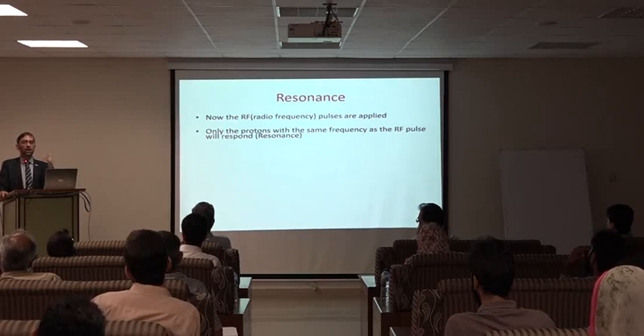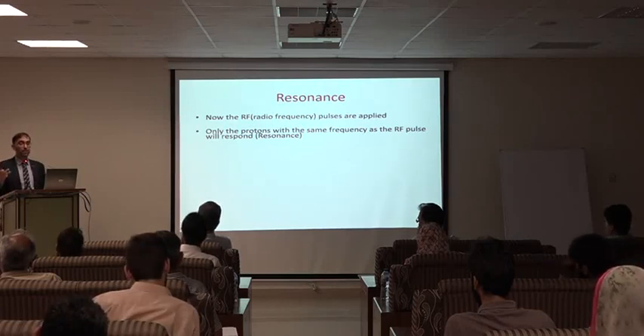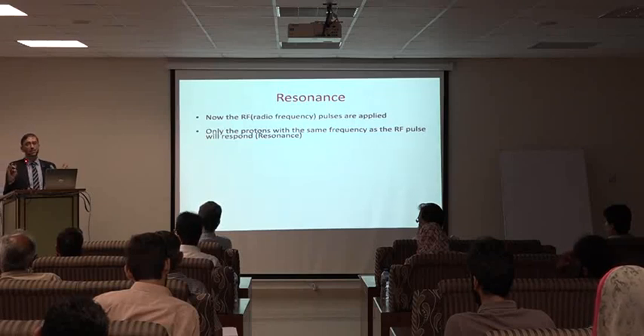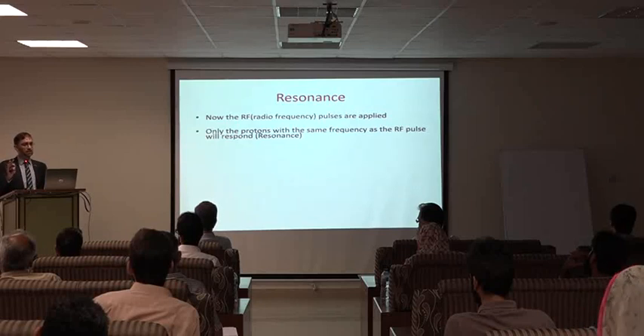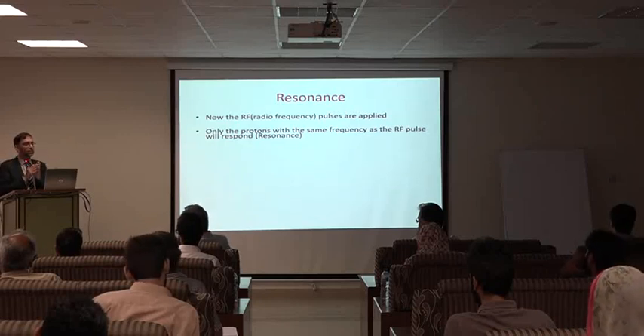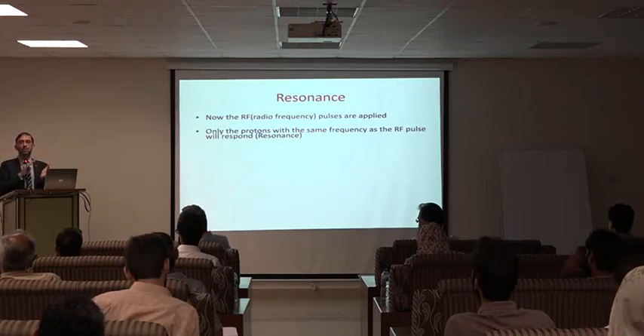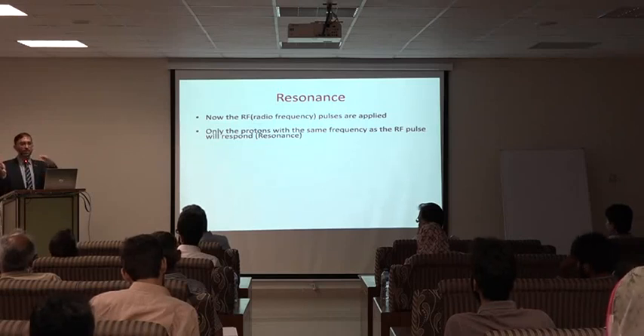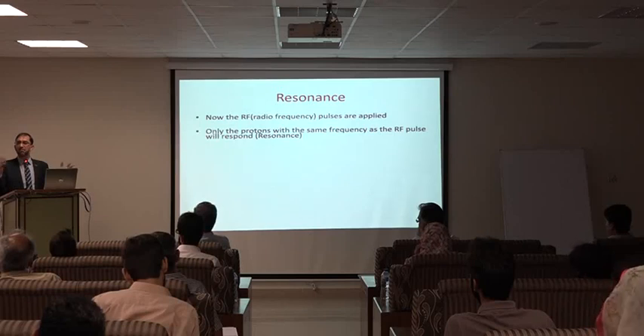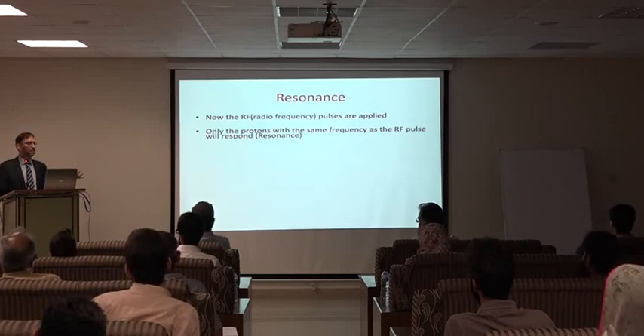For example, as part of my PhD, I myself designed a transmitter coil and the receiver coils as well. We were operating a 1.5 Tesla scanner, at something around 63 megahertz. That was the central frequency. And then there was plus or minus 0.5 megahertz. So the range of frequencies used to be between 62 and 64 megahertz, not more than that. So that much variation, and it depends.